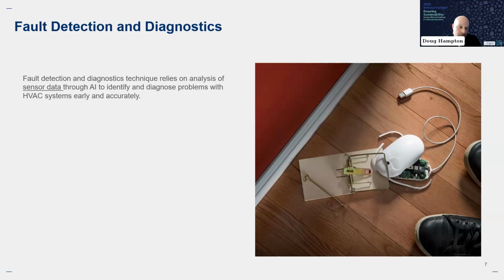It's about being able to sort through the noise and bypass some of that. If the AI, or any analytic for that matter, can sort out the low-hanging fruit - which things aren't performing well, which set points are out of range - this allows me to give better value to the customer because I have those priorities and can go directly to them. So what can we fix now as opposed to fixing or replacing later? Just because a machine's working well doesn't mean it's working its best.